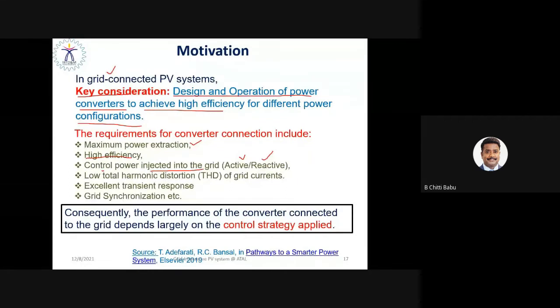Reactive power control is essential to maintain the voltage profile constant. Active power control is very essential to maintain the frequency constant, because frequency is a key parameter that governs power system security, and voltage profile is a key component that governs power system reliability. So that is the main motivation of grid connection requirements, which include controllable active and reactive power that must be injected into the utility grid.